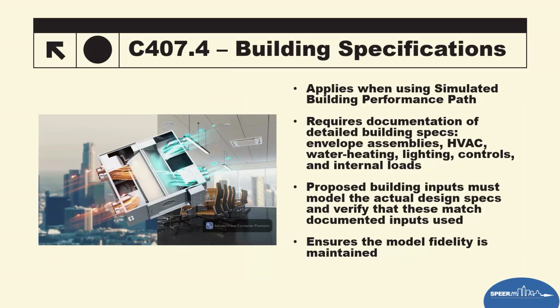And then building specific. So C407.4, the 2024 IECC emphasizes that when you choose the performance path, you must detail and commit to the actual building specifications, basically covering everything from insulation to glazing to the equipment efficiencies to the controls. The modeling must reflect those specifications, and during construction and document review, you'll need to verify that the implementation of these systems matches the modeled ones. I get this a lot from people: a model is built, it's handed in for permit, the permit is given out, and then the building is built completely different. So it is clear that once this modeling is done, you should follow that in the field. So for construction, documentation, commissioning, all of that is verifying that it actually meets what was modeled. This prevents what we call model-to-build drift. It basically ensures the predicted energy savings from the simulation are credible and that what was modeled was actually installed.